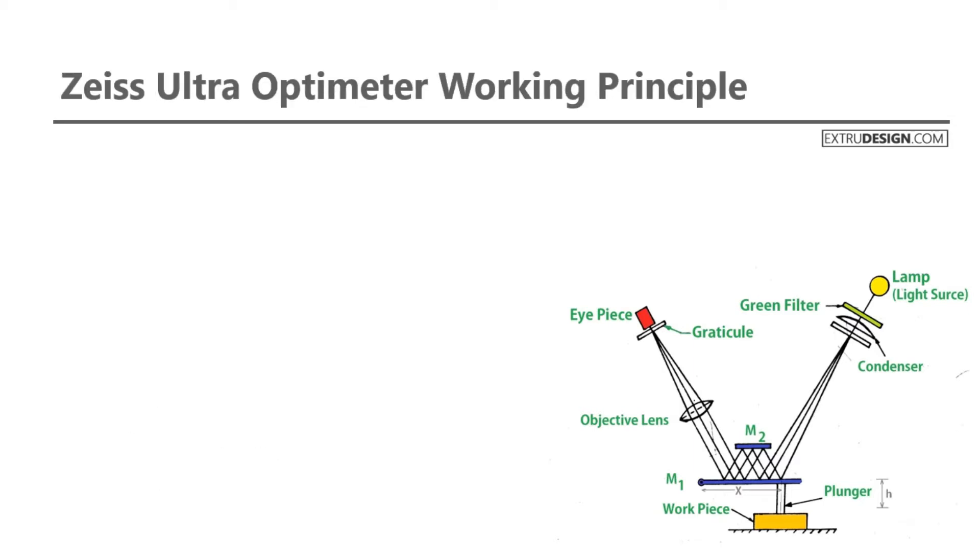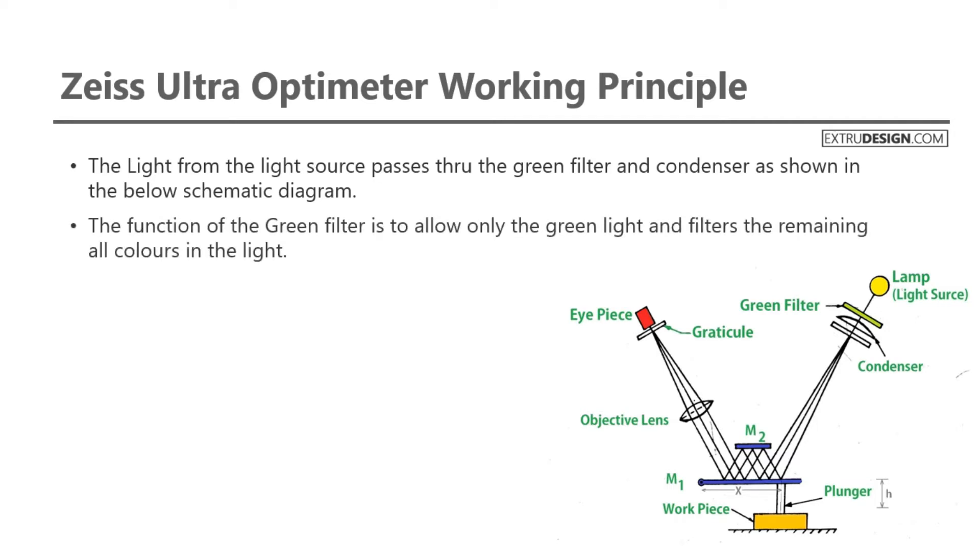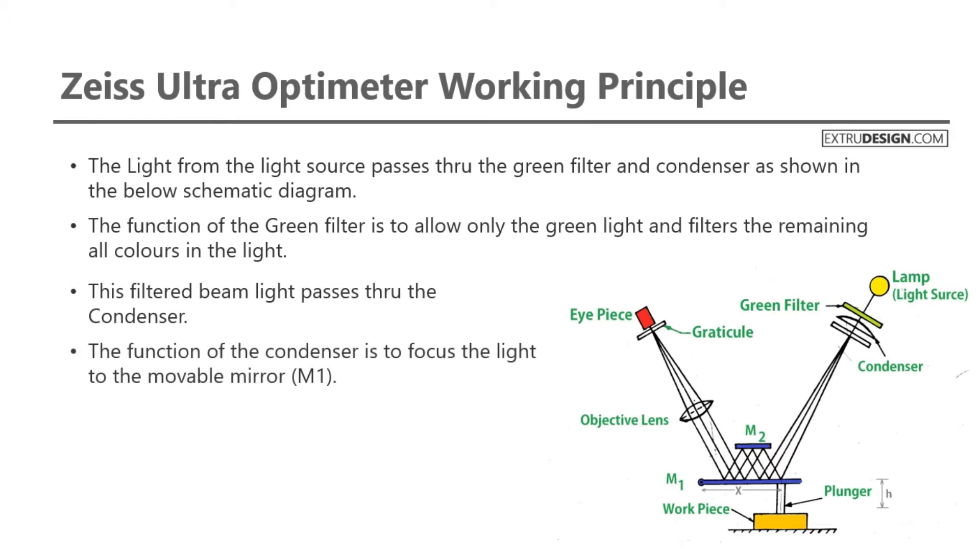Let's see how the Zeiss Ultra Optimeter works. The light from the light source passes through the green filter and condenser, as shown in the schematic diagram. The function of the green filter is to allow only green light and filter out all remaining colors. This filtered beam then passes through the condenser, whose function is to focus the light onto the movable mirror, M1.